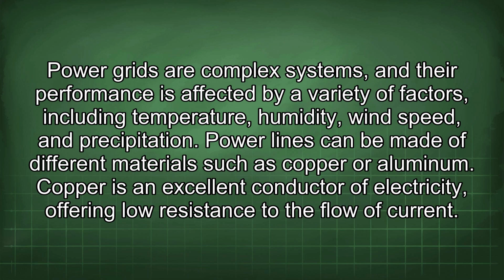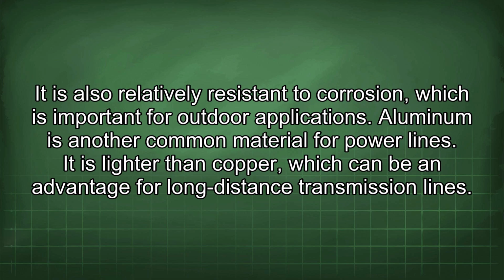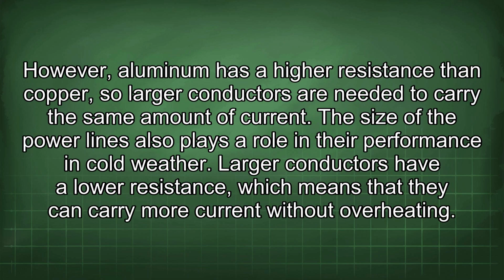Copper is an excellent conductor of electricity, offering low resistance to the flow of current. It is also relatively resistant to corrosion, which is important for outdoor applications. Aluminum is another common material for power lines. It is lighter than copper, which can be an advantage for long-distance transmission lines. However, aluminum has a higher resistance than copper, so larger conductors are needed to carry the same amount of current.